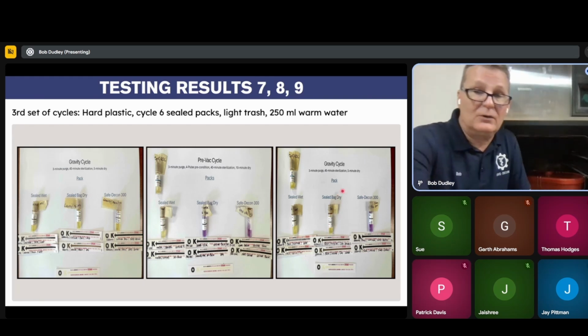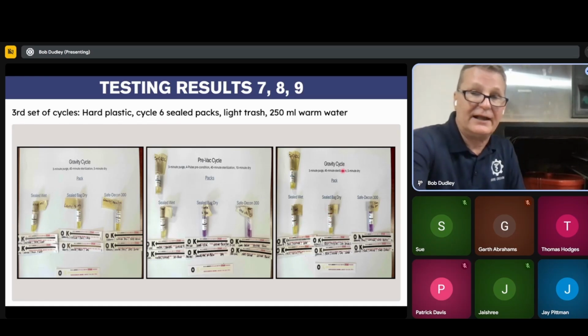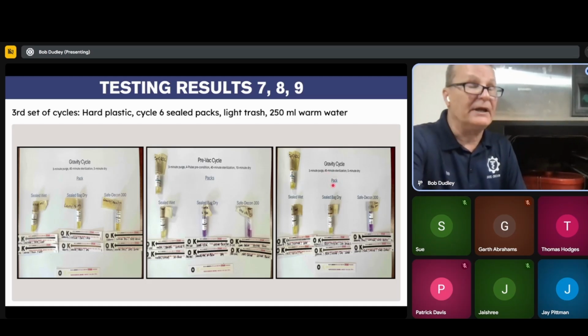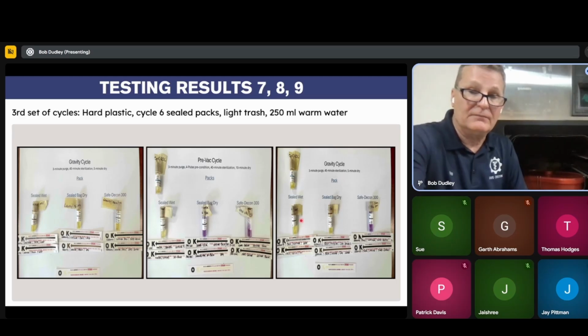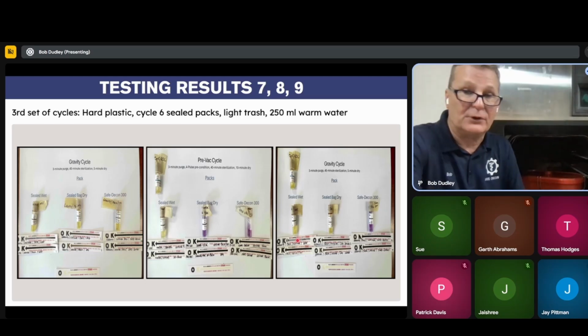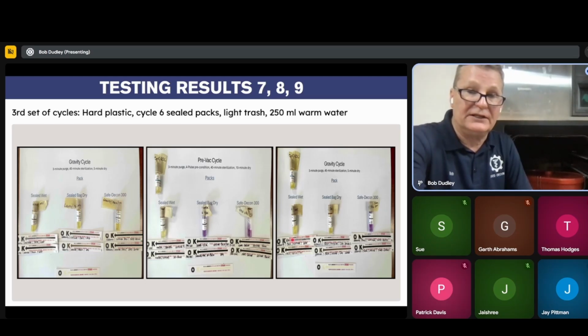So now on the packs here, I ran a 30-minute, 40-minute sterilization. And you can see, this pack here I didn't tie down. I just flipped it, like you saw in the very beginning. It wasn't a very tight pack, and it was a 40-minute cycle with the loose pack in there. Both of these bags did bust during that cycle. I don't know exactly when during sterilization, but they did, and you can see that steam did permeate. This one got wet. When the bag burst on this one, it did flip into the liquids, but you can see that we got the okay. Again, chemical strips, bad BIs.